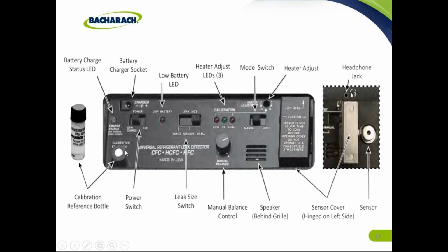Over here, we have a calibration bottle. This is the bottle I talked about where you have a foil paper cover on it. You peel it off, and this sets in here. You take the probe, you swish it over that leak detector, and you will get these lights flashing to tell you if the sensor is at the proper heat. If you run the probe across this calibration gas, and it goes from low, a red on low, to a green okay, and then back to low, it's working perfectly.